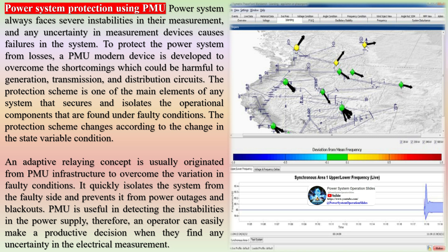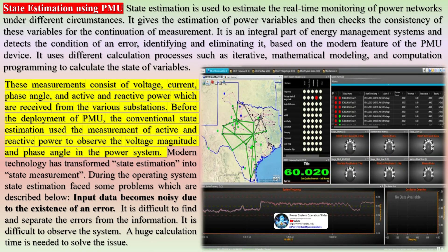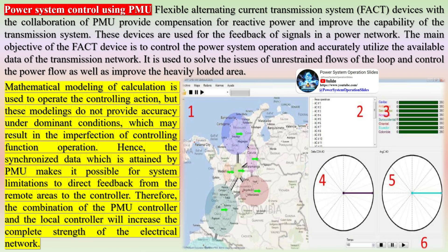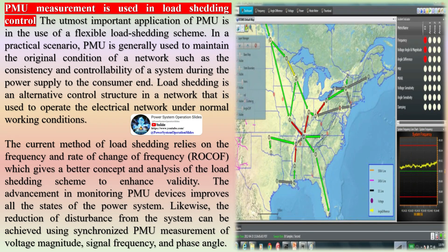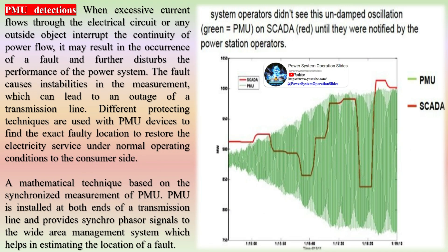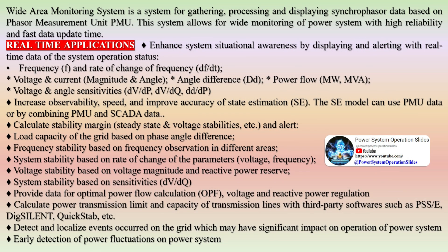The performance of the SCADA system relies on steady-state power flow analysis, while the operation of the PMU is based on the real-time synchronized measurement of voltage and current phasors with high accuracy and faster sampling rate. In recent years, progress in system monitoring, power, and control has been possible because of wide-area monitoring systems that implement phasor measurement units (PMUs). When a PMU is installed on a node, it is possible to measure voltage and current phasors in some or all adjacent areas to this node with high accuracy, enhancing the efficiency of methods for fault detection and allowing decisions to be made to keep system stability.